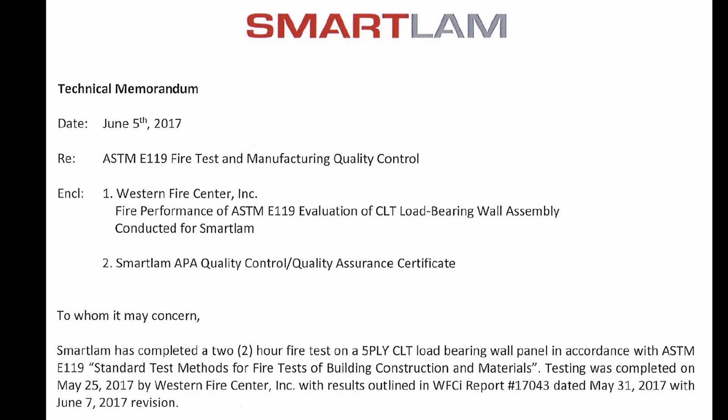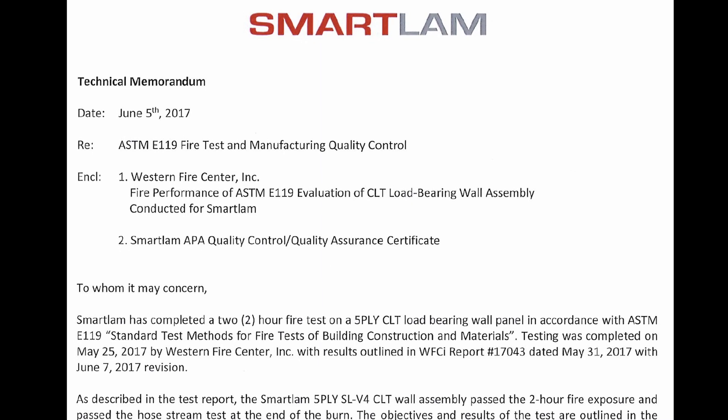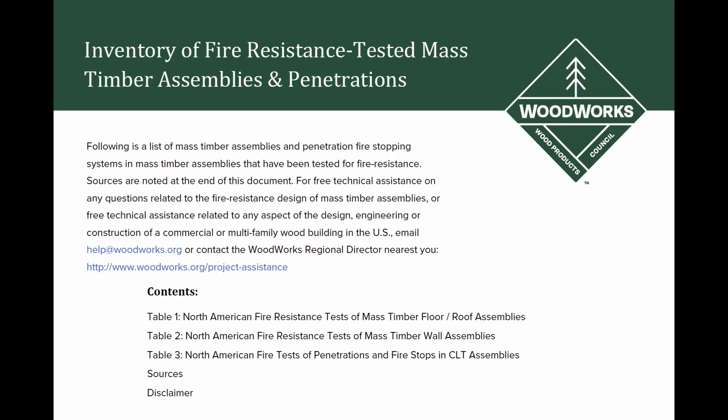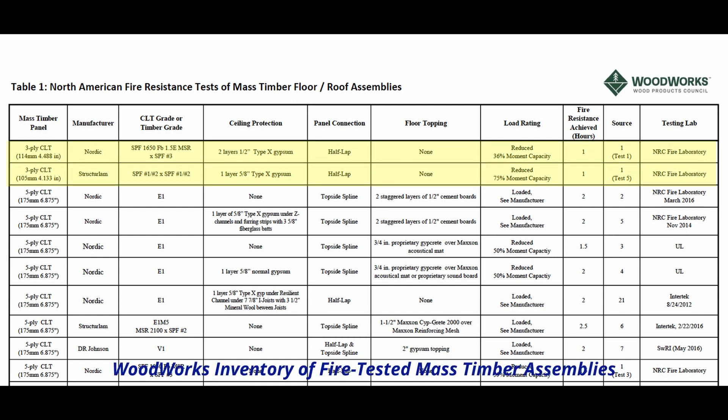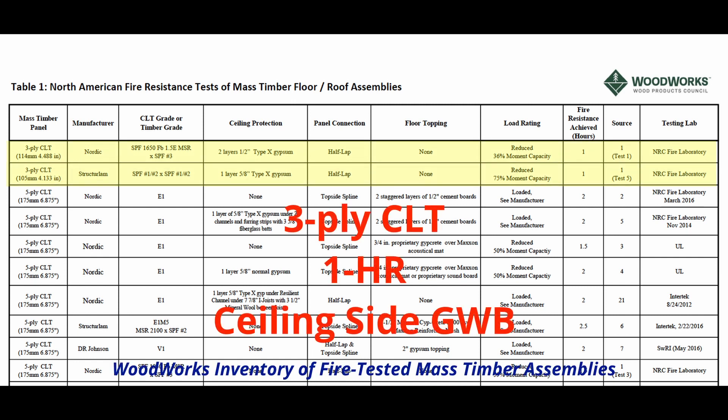One of the valid options for demonstrating the fire resistance rating of an assembly is through citing the test reports from an E119 fire test. Woodworks has compiled over 50 mass timber E119 fire-tested assemblies for floor, roof, and wall applications. So if we're looking at that first example of a three-ply CLT floor panel with direct applied gypsum wallboard to the ceiling, we could turn to this inventory of fire-tested assemblies and find that there is an option within this inventory for such a condition. That could be the basis for demonstrating on this project how it meets the code requirements for a fire resistance rating of a mass timber panel with direct applied gypsum wallboard.